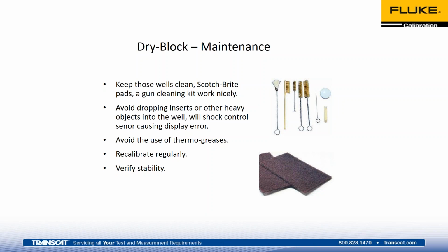For cleaning the outside of the inserts, Scotch-Brite works really well. Sometimes I've seen them get fairly corroded over the years, and if you do, you can go to a light grit sandpaper. Usually I'd stick to 600 or so. Don't get real aggressive with it. And then again, just recalibrate regularly if you are not using a reference, and always watch your stability.